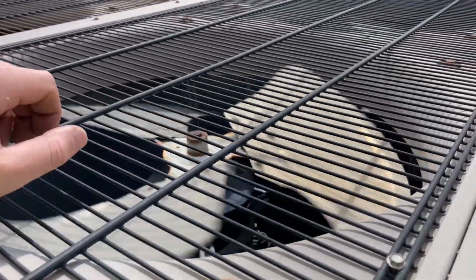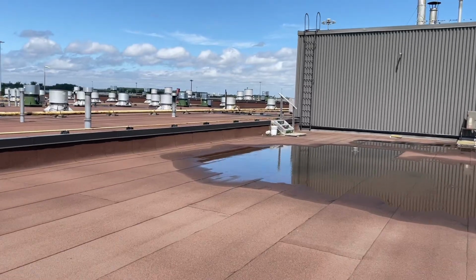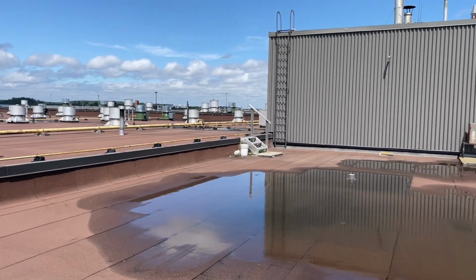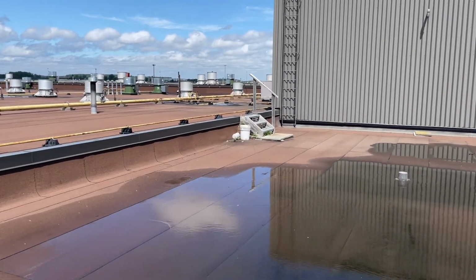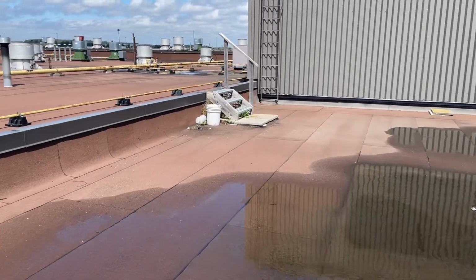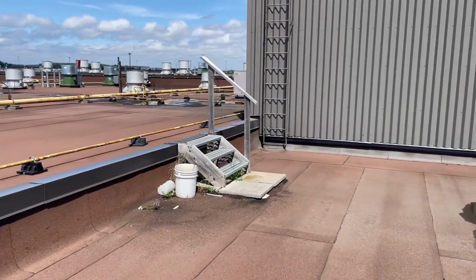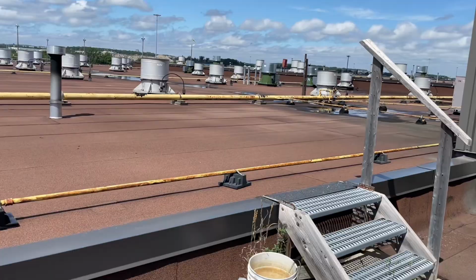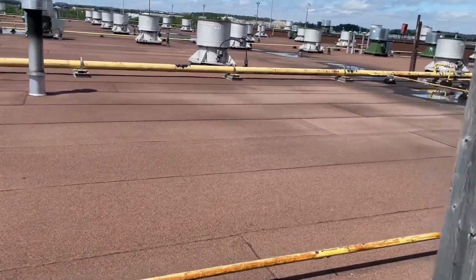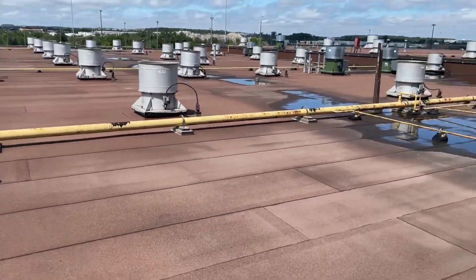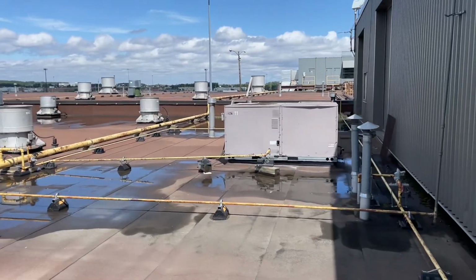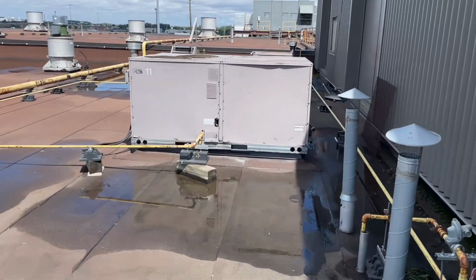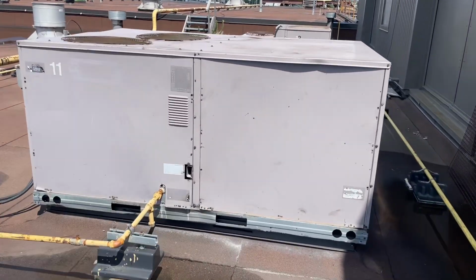On to the next. And our final call of the day, well, I wouldn't really say it's a service call. We need to size up a new rooftop install. So what that means is we're going to be measuring the curb and the adapter if it has one, checking voltage, and I'll show you guys how to do that now. Here's our rooftop here. Let's go.